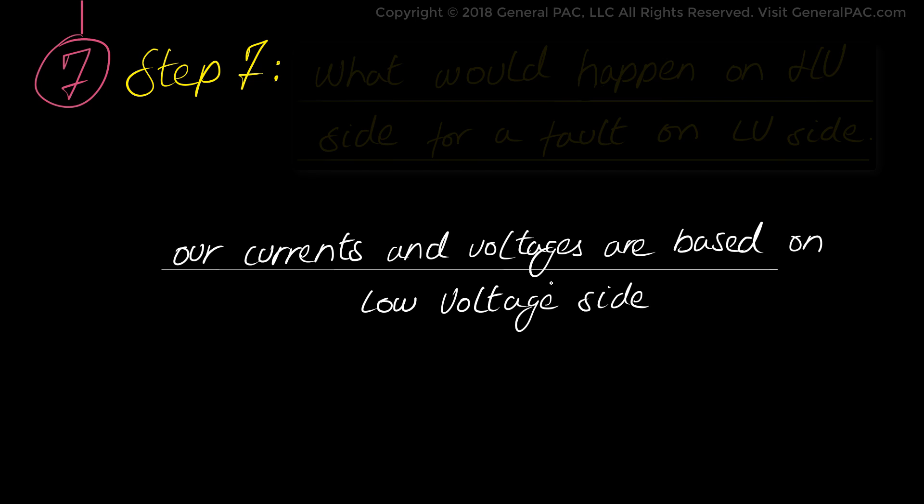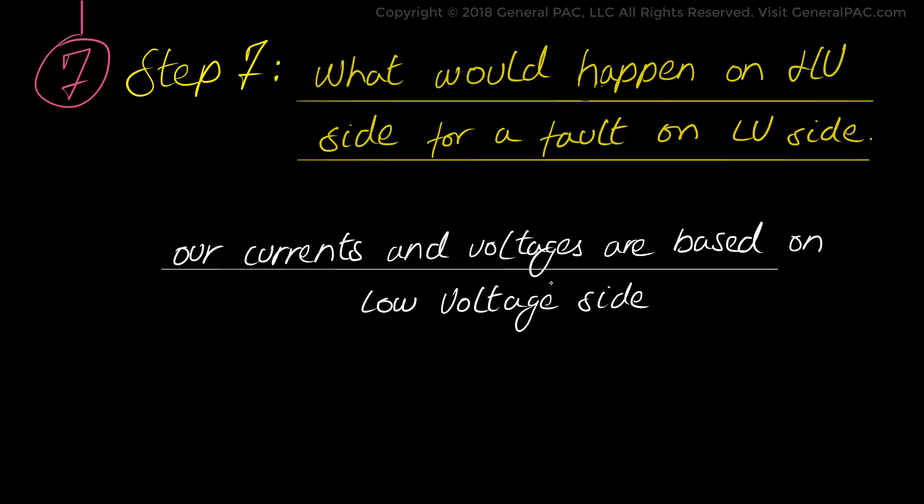Now in step 7, the 7th step, this step can actually be skipped. And we are calculating the fault that occurs on the low voltage side of the transformer. All of our current and voltage calculated quantities are based off the low voltage side. Now if we wanted to analyze what would happen on the high voltage side of the transformer, for a fault that occurs on the low voltage side, this requires a very special step.